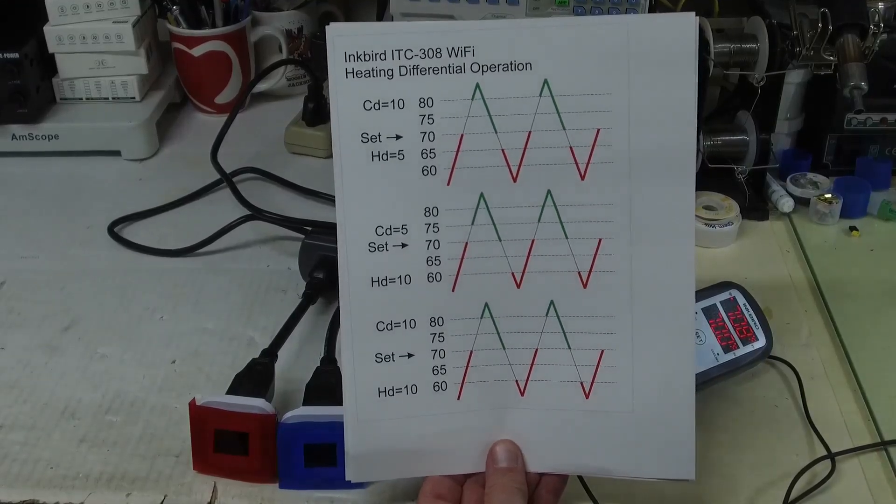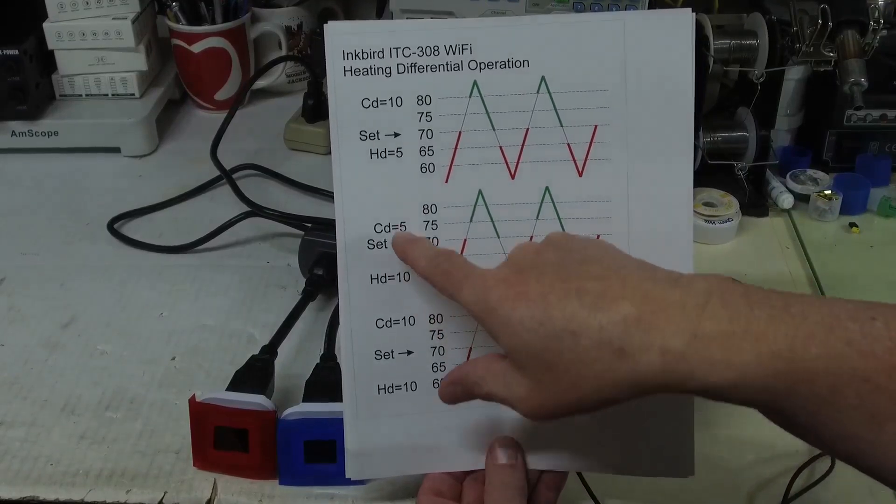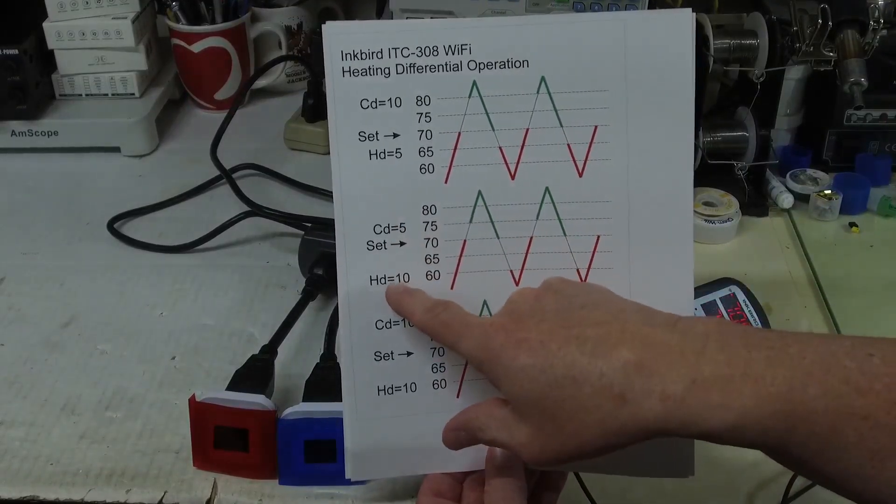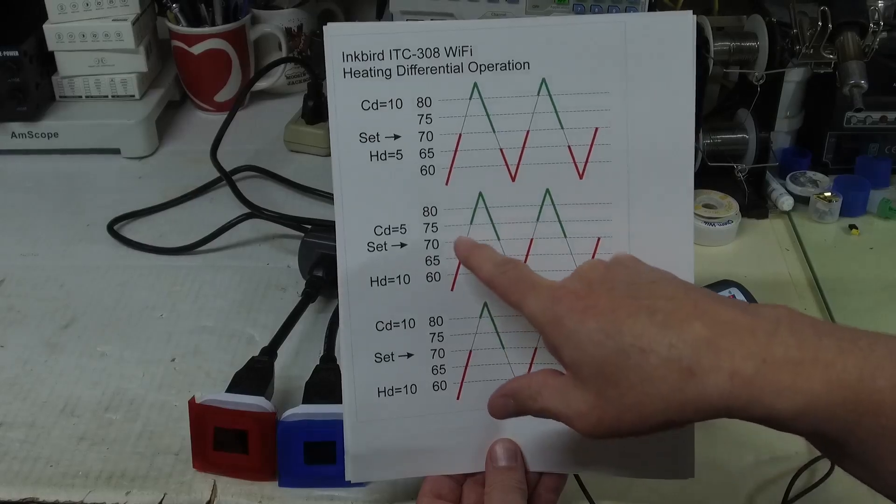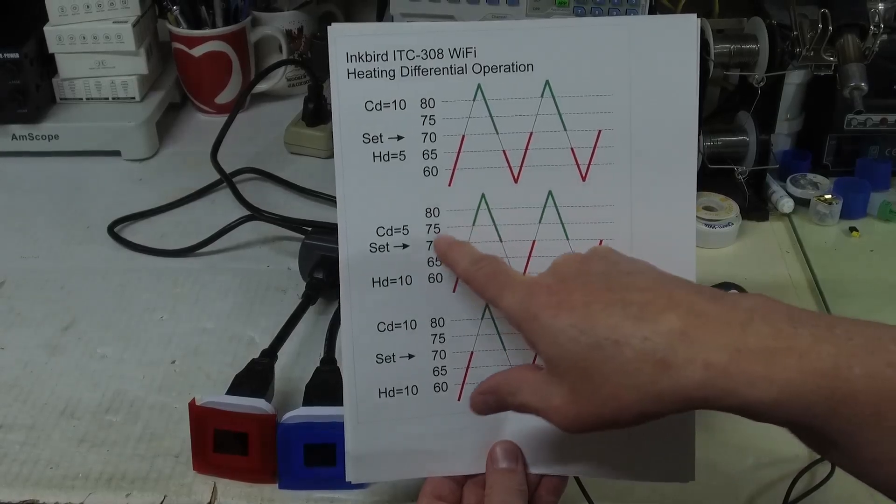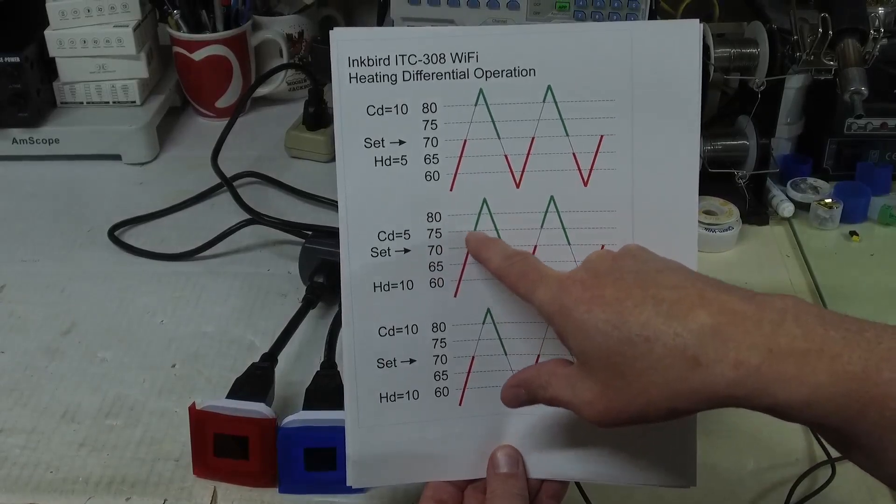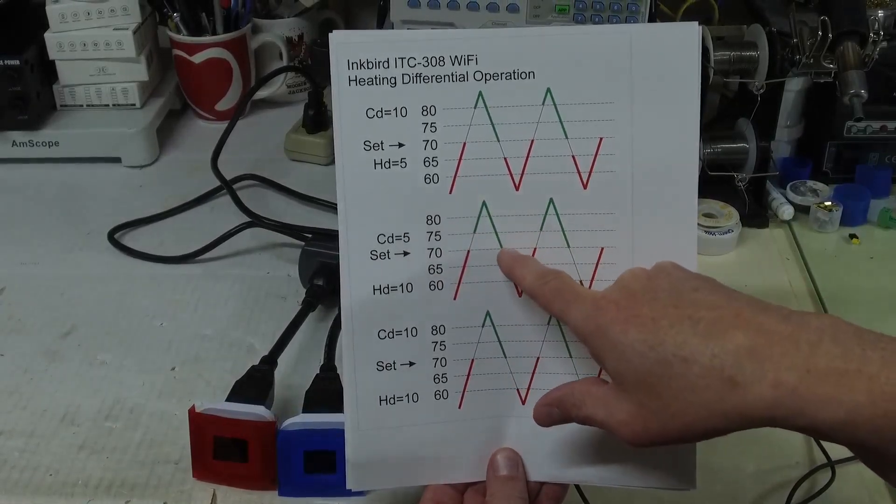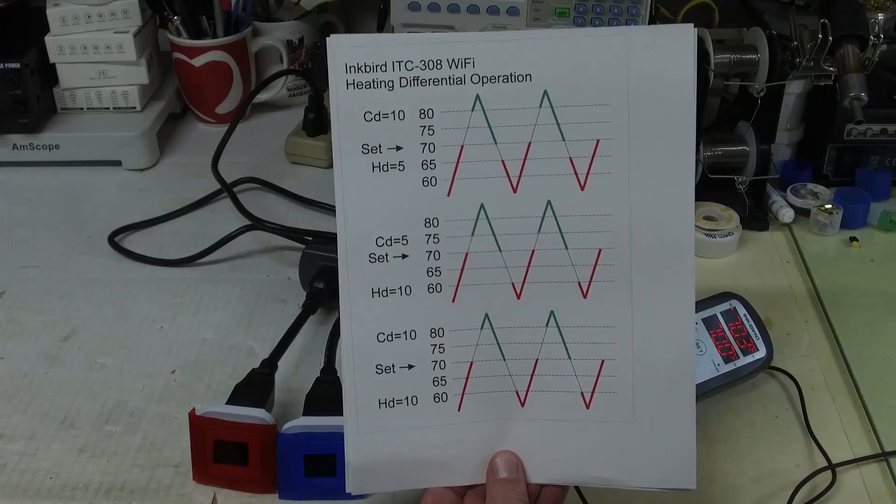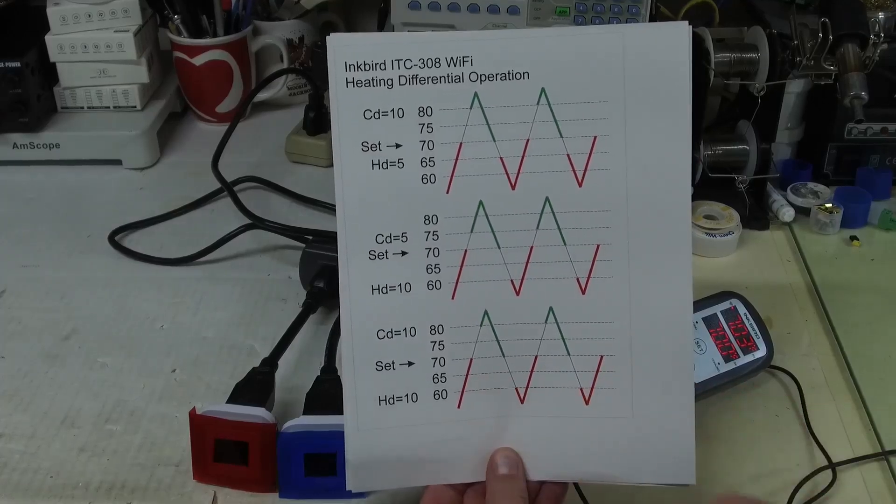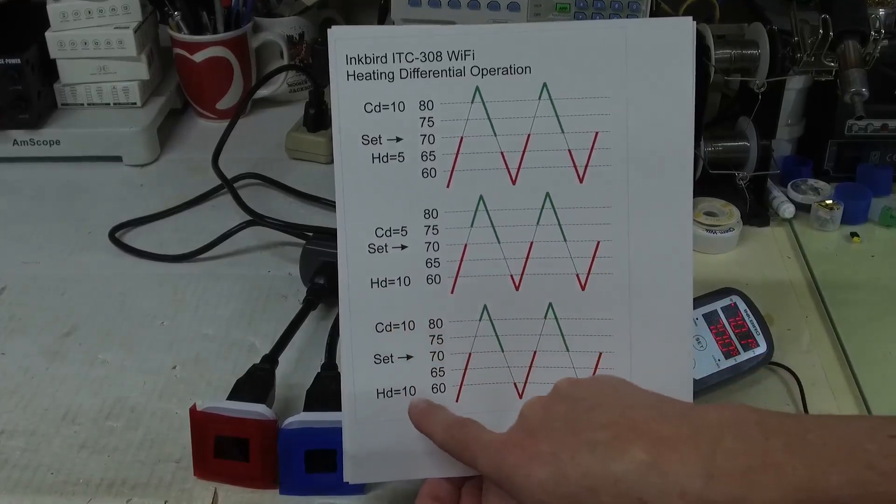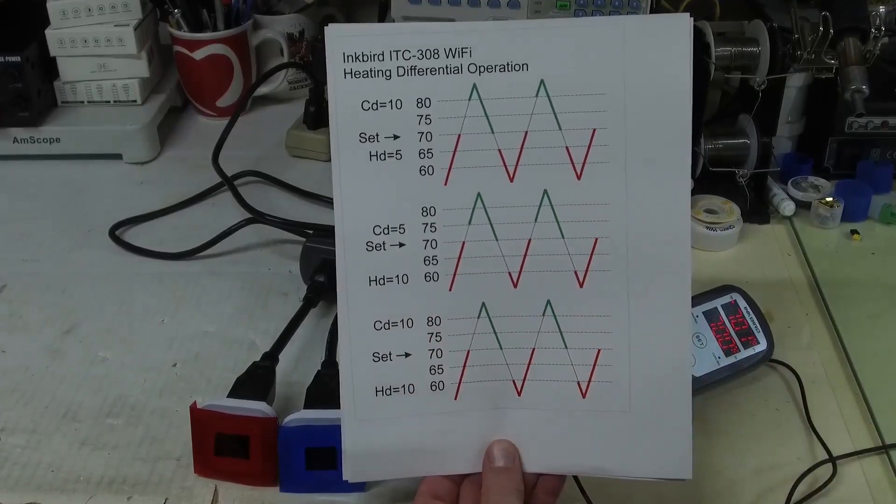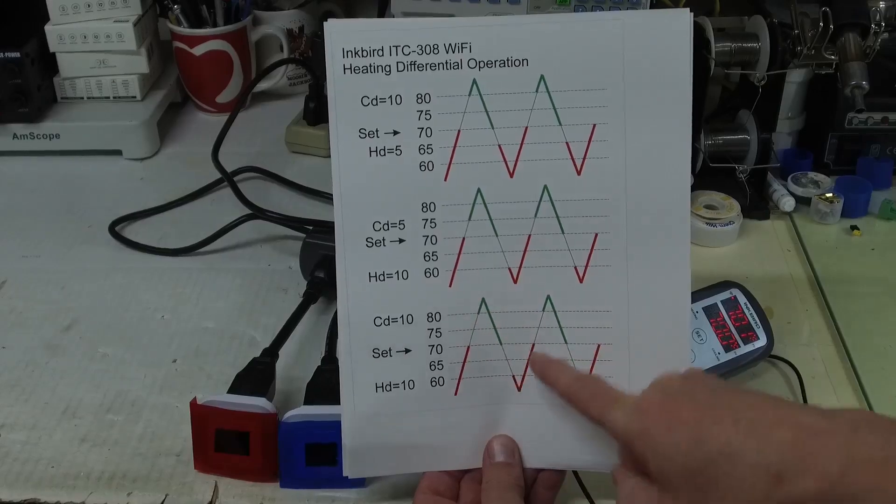So that's interesting to me. And here I've reversed the heating and the cooling differentials, and you can see here that the cooling will turn on at 75 but not turn off until 70. The graph is a little different. And if we have the cooling differential and the heating differential set at the same temperature, we will end up with this type of graph.